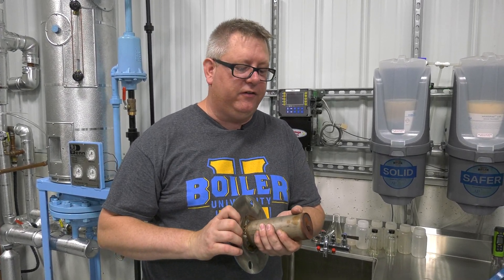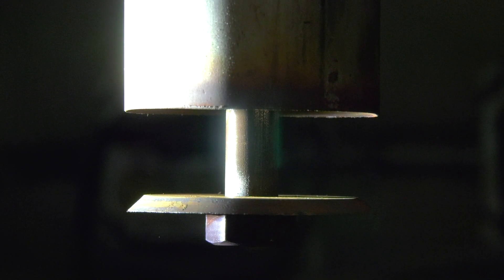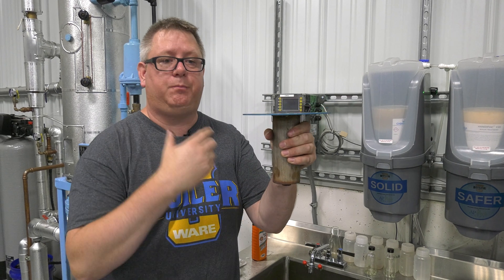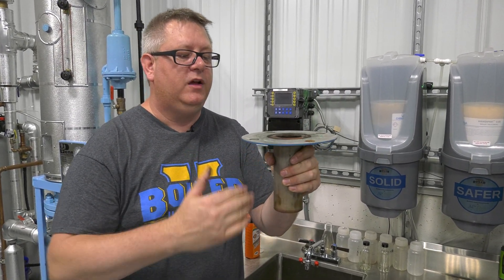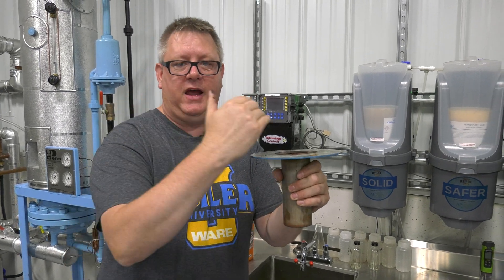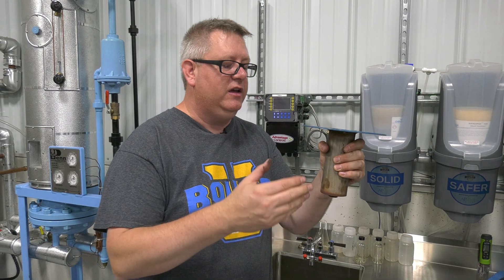Secondly, if this were to fail open, it ceases to function as a check valve. And if it doesn't close properly due to a spring breaking or wear and tear of the nozzle, steam can back up this pipe.